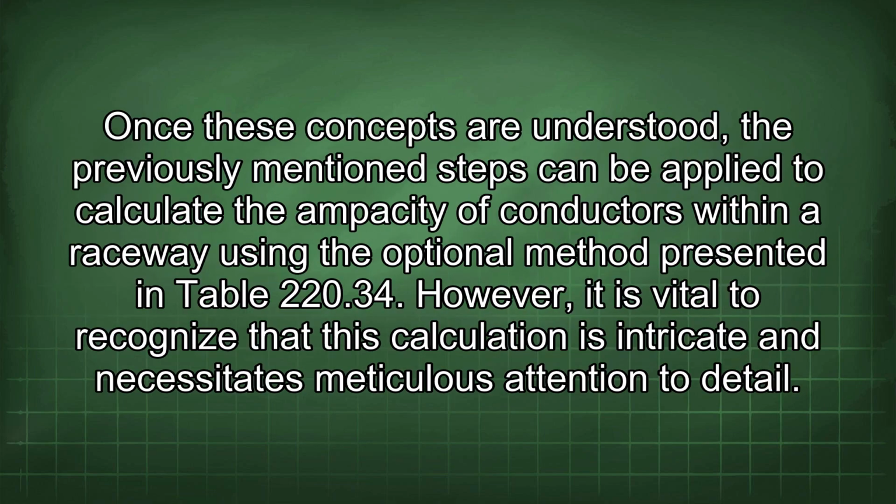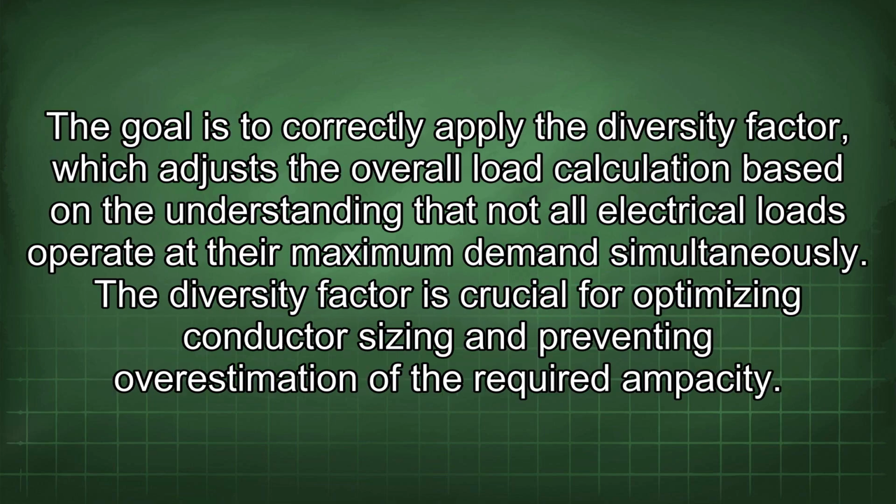Once these concepts are understood, the previously mentioned steps can be applied to calculate the ampacity of conductors within a raceway using the optional method presented in Table 220.34. However, it is vital to recognize that this calculation is intricate and necessitates meticulous attention to detail. The goal is to correctly apply the diversity factor, which adjusts the overall load calculation based on the understanding that not all electrical loads operate at their maximum demand simultaneously. The diversity factor is crucial for optimizing conductor sizing and preventing overestimation of the required ampacity.